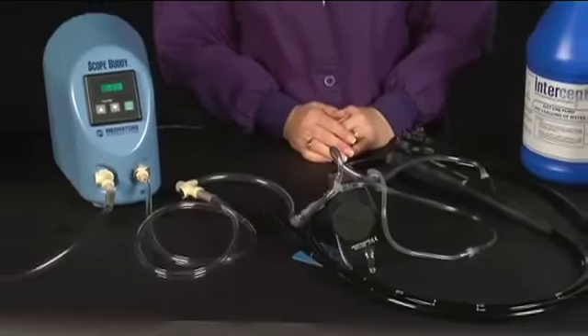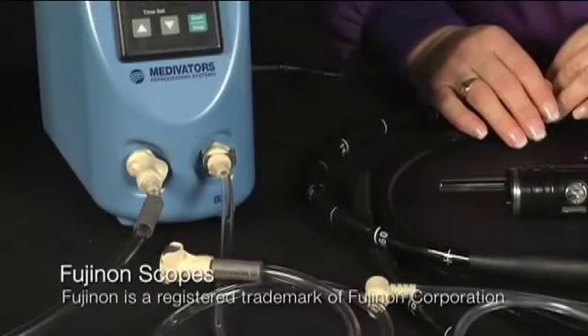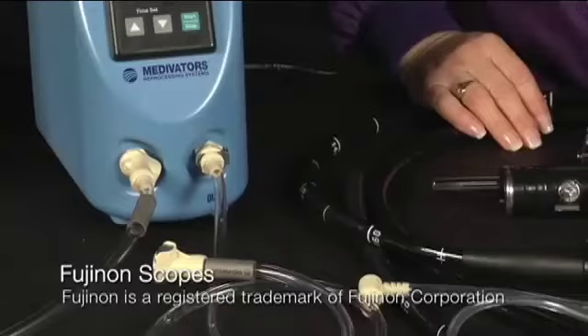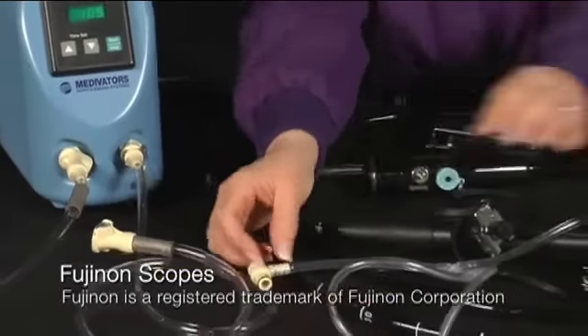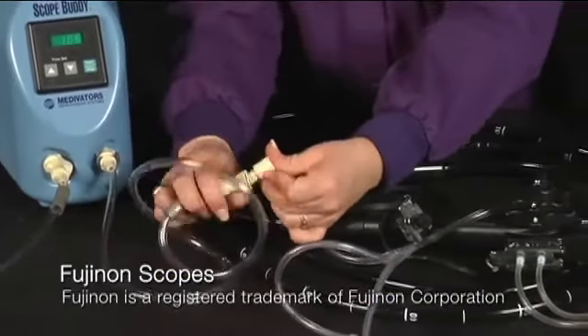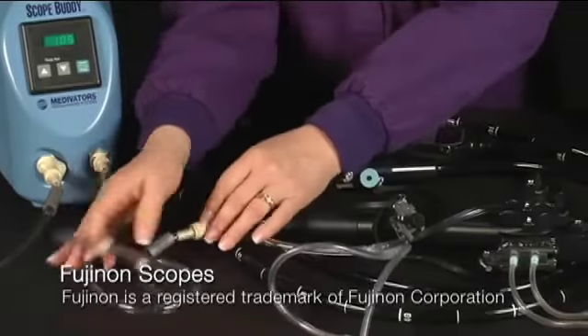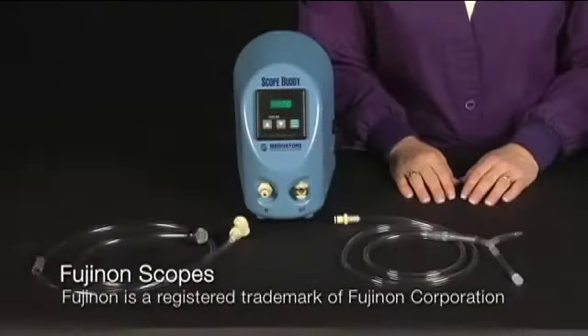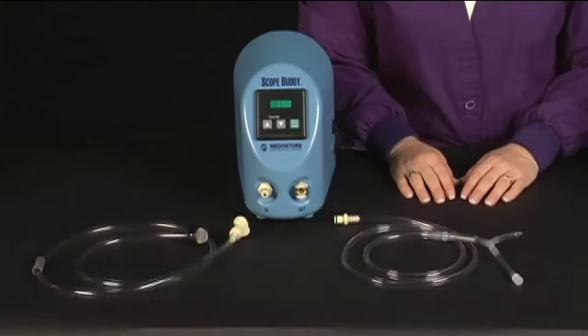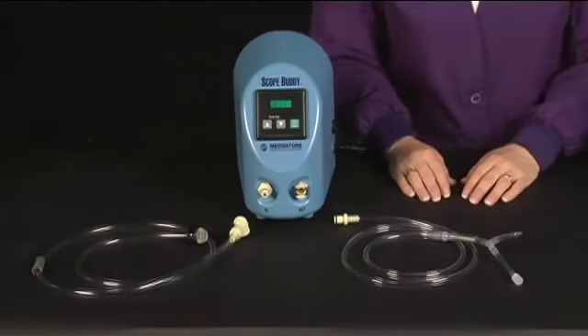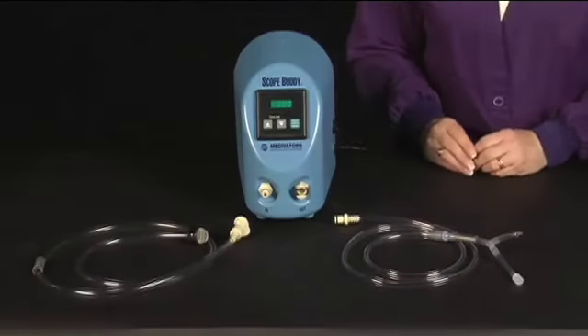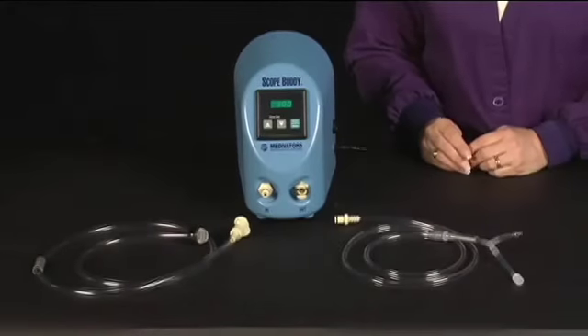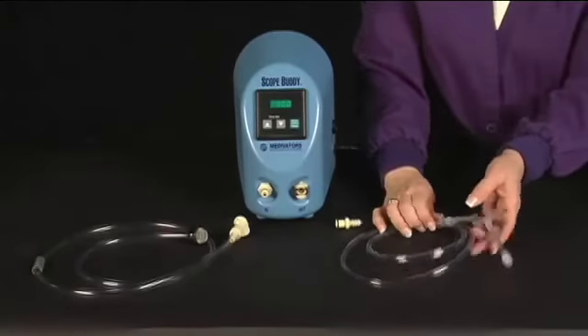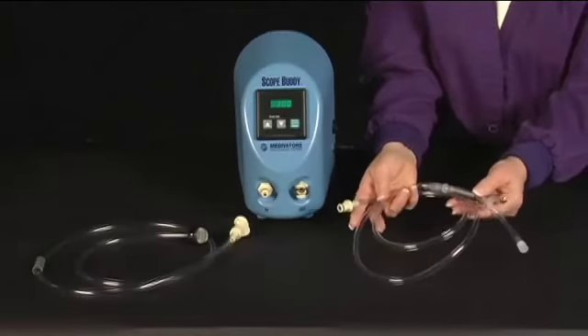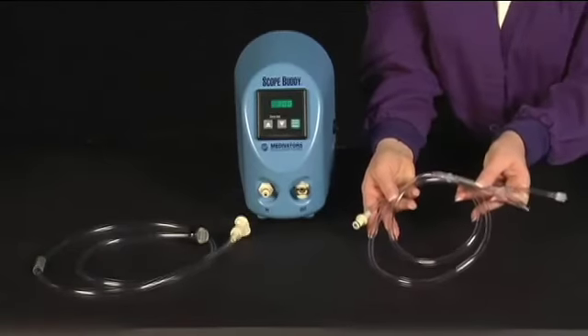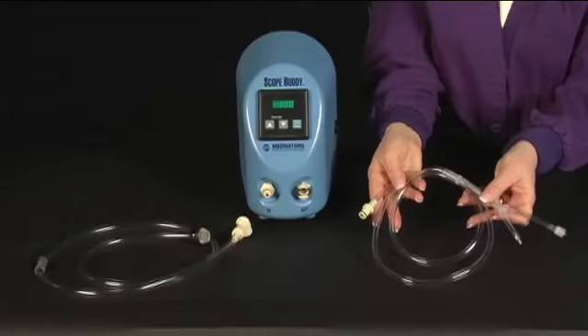For Fujinon endoscopes, all channels of a Fujinon endoscope can be flushed simultaneously using the appropriate DSD hookup with the exception of the forward water jet channel or the elevator wire channel of a duodenoscope. A Fujinon endoscope's forward water jet channel or elevator wire channel of a Fujinon duodenoscope must be flushed separately from the other channels using the elevator wire channel hookup. First, use the appropriate DSD hookup attached to the Fujinon cleaning adapter to flush all other channels.